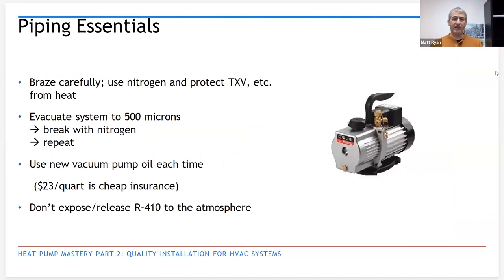Systems where we're brazing, not flaring, make sure you are purging nitrogen while you do your brazing. Protect the TXV, the valves. Those are heat sensitive. You can't overheat them and damage them. If we're not purging nitrogen, it's just a matter of time before you'll be back replacing the TXV. That's one that we have to really hammer home with the install crews, because they're not always necessarily aware of that from our service team, where maybe a year or two down the road, not purging caused some buildup, and then that buildup eventually clogs that TXV or takes it out.